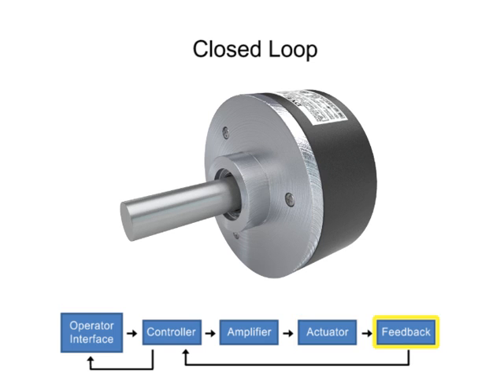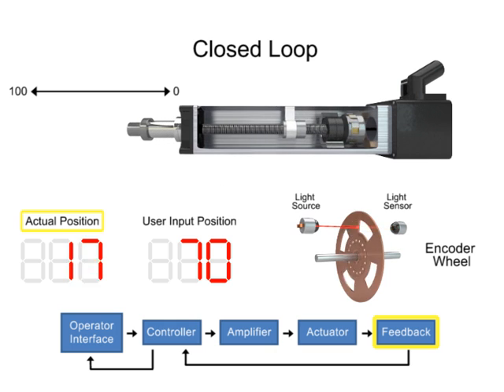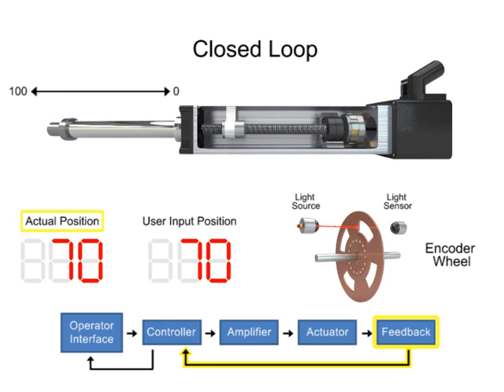The feedback device, usually an encoder or position sensing device, recognizes the motor position and reports the result back to the controller. As the encoder rotates, position and speed information are relayed to the controller and compared to the user input.